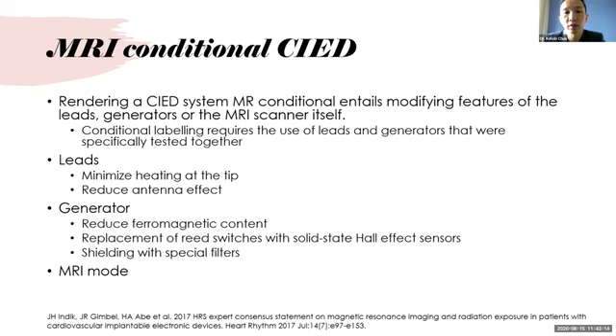Shielding with special filters limits the transfer of certain frequencies and dissipates energy, thereby reducing the risk of potential damage to the circuitry. Certain devices also have an MRI mode, which also features pre-scan system integrity checks. It uses asynchronous pacing, non-sensing modes, disabling of tachycardia detection, increasing the output during the scan, and restoration of pre-scan program states and values. So many companies have this. You should talk to your device representative. MRI modes are easily programmable.